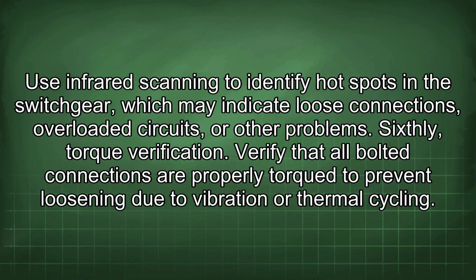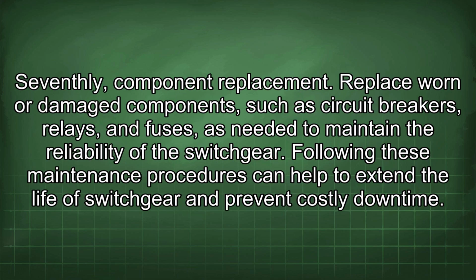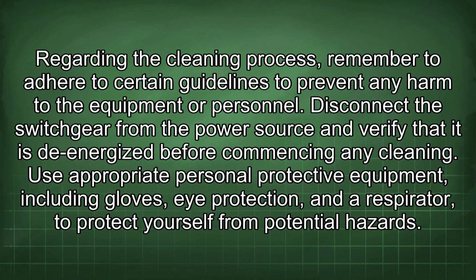Verify that all bolted connections are properly torqued to prevent loosening due to vibration or thermal cycling. Seventhly, component replacement. Replace worn or damaged components, such as circuit breakers, relays, and fuses, as needed to maintain the reliability of the switchgear. Following these maintenance procedures can help to extend the life of switchgear and prevent costly downtime. Regarding the cleaning process, remember to adhere to certain guidelines to prevent any harm to the equipment or personnel.